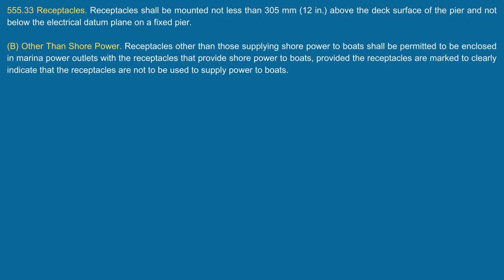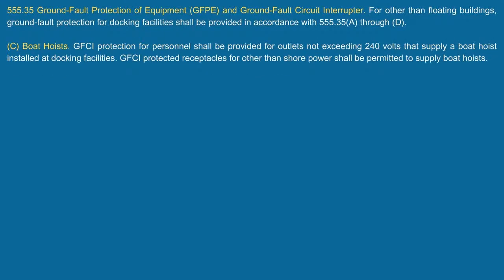Me and you, we uncovered the one on EVSE, because the EVSE manufacturer instructions said GFCI protection is not required if you hardwire it. The only time GFCI protection would be required is if you cord and plug connect it, because if you go into 625, I think it was 62540 or 62530 something, it says all receptacle outlets must be GFCI protected. It doesn't say anything about hardwired being an outlet.